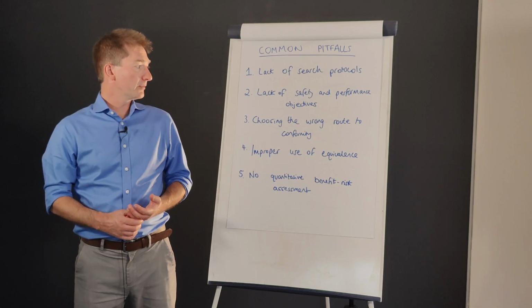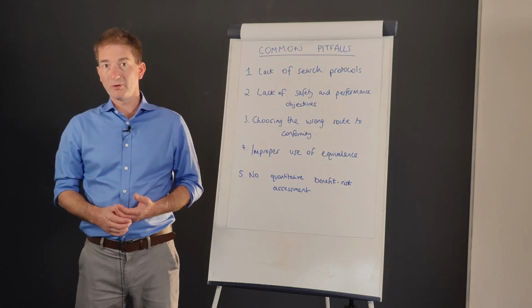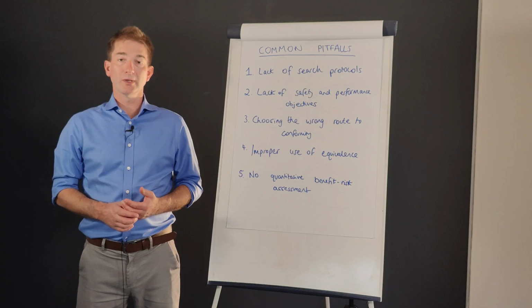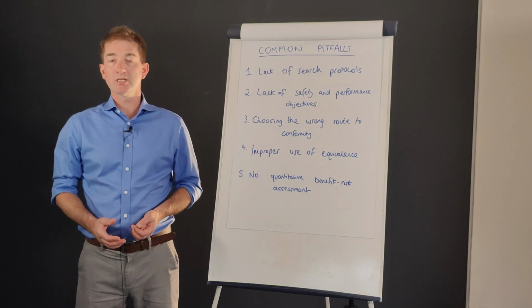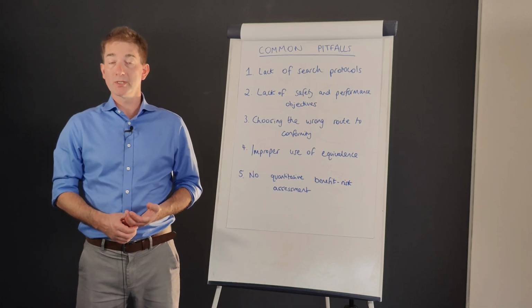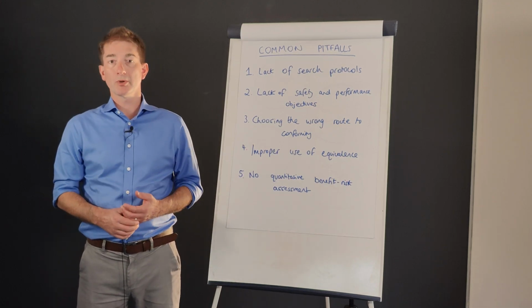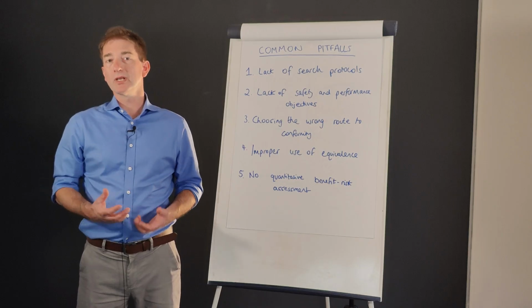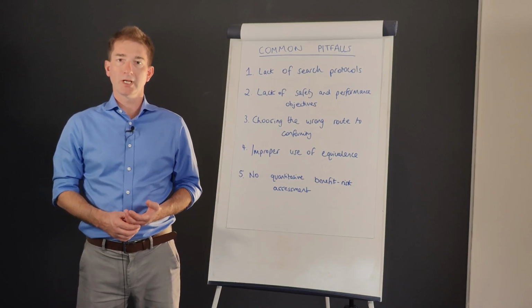The next common pitfall that we see is choosing the wrong route to conformity. This is very easy to fall into for a number of reasons. A lot of legacy devices may have used the equivalence route to conformity, where you're relying on data from another product. But claiming equivalence under the EU MDR is actually a lot more difficult than it used to be.